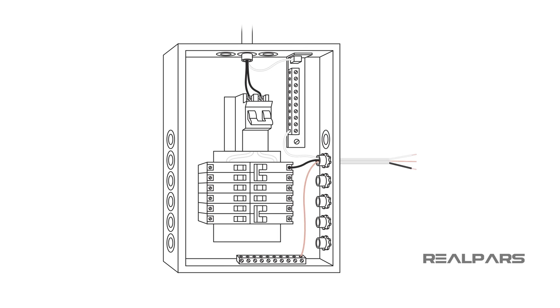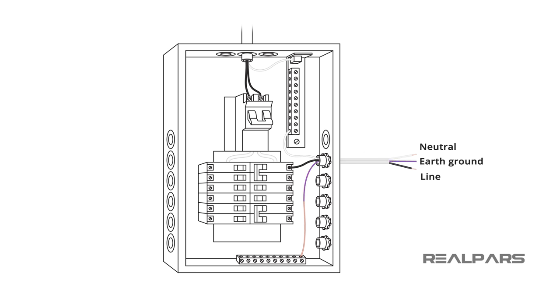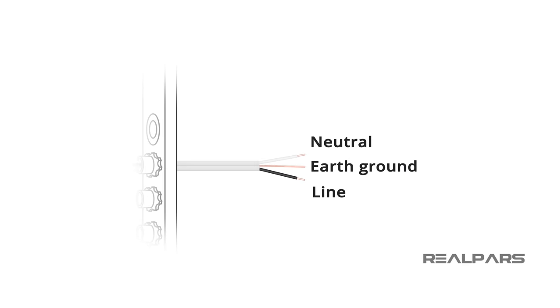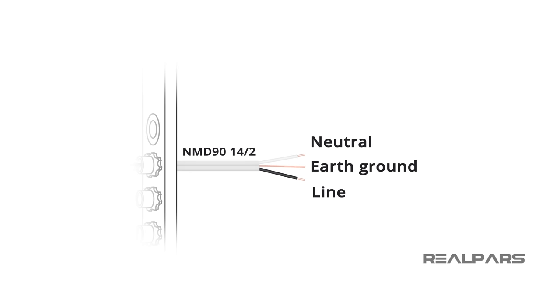In North America, the two electrical power supply wires are called Line and Neutral and originate from a circuit breaker in an electrical panel. The Line wire has black insulation and the Neutral wire has white insulation. The cable that leaves the electrical panel will contain these two wires plus a third wire which is connected to earth ground. The earth ground wire has no insulation. The cable is referred to as NMD-90-14-2 because of the size of the conductors and the number of wires inside.